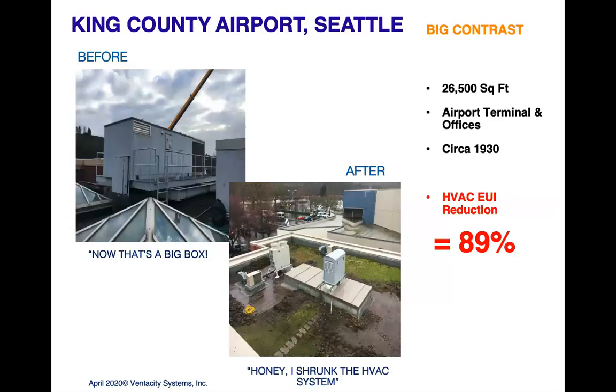This is King County Airport. This is a 26,000 square foot building. It's an old, circa 1930s brick stone building. Nothing insulated, real well insulated or anything there. We started with 3 of these very large rooftop units on the roof and finished with 3 1,000 CFM HRVs and 4 heat pump systems. And once we had climate normalized and done all the data over a year's period, it came down at 89% reduction in energy, which is for the HVAC energy, which is just off the charts. So extremely successful there.